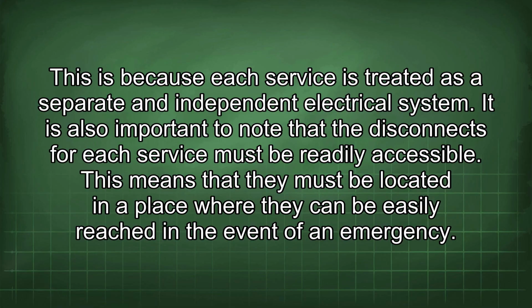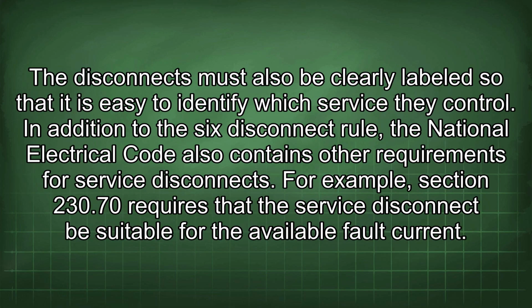It is also important to note that the disconnects for each service must be readily accessible. This means that they must be located in a place where they can be easily reached in the event of an emergency. The disconnects must also be clearly labeled so that it is easy to identify which service they control. In addition to the 6 disconnect rule, the National Electrical Code also contains other requirements for service disconnects. For example, Section 230.70 requires that the service disconnect be suitable for the available fault current.